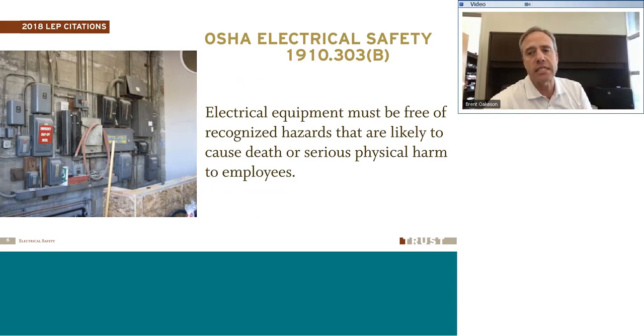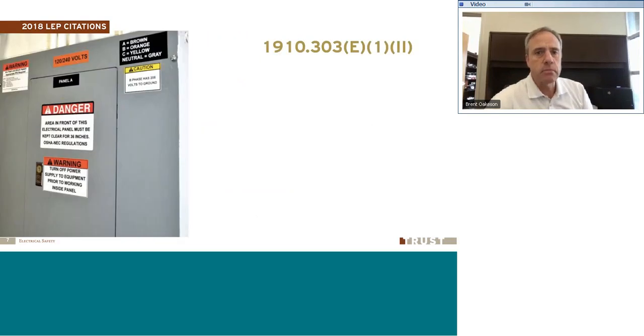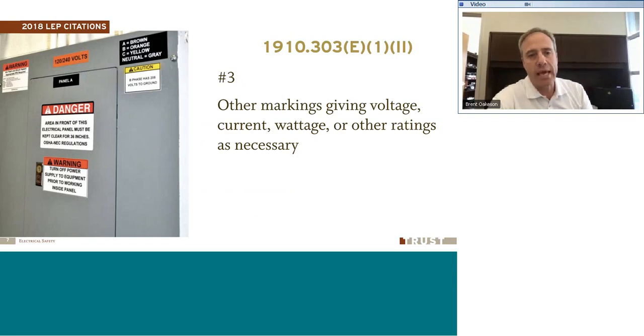So there's a lot of different things in here. What we saw as being one of the most common ones was 1910.303(E)(1)(II), which was markings on the electrical panels. And so the electrical panel, we need to have certain markings on there. The real basic ones are for voltage, current, wattage, and so forth, so that when we look at this panel, we really need to know how much power is inside of there. Some requirements are going to depend on whether we're under or over 600 volts. But we really need to have some basic markings on the electrical panel. So this was one of the most common ones.